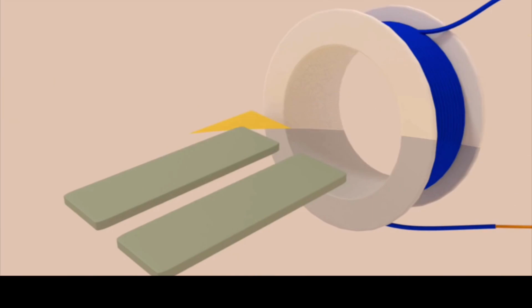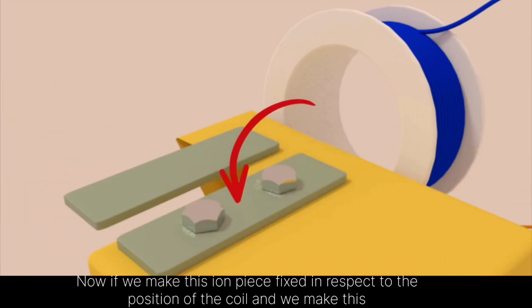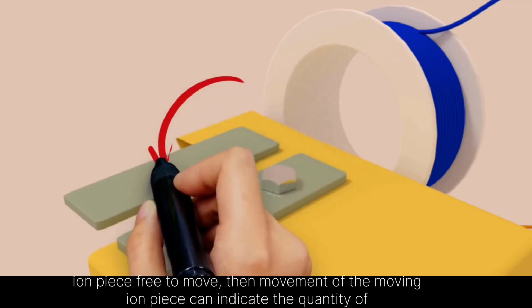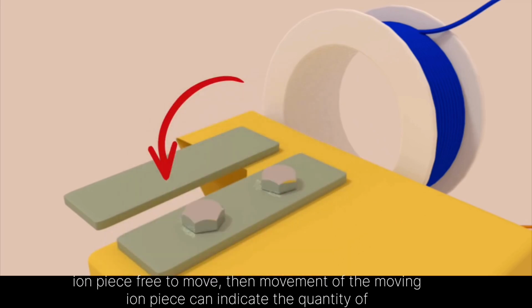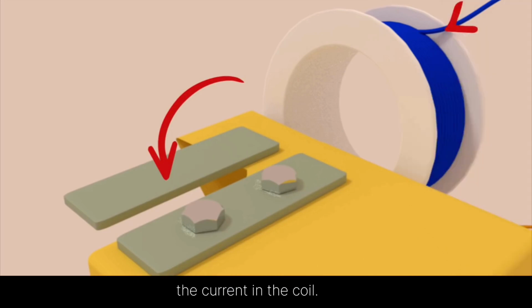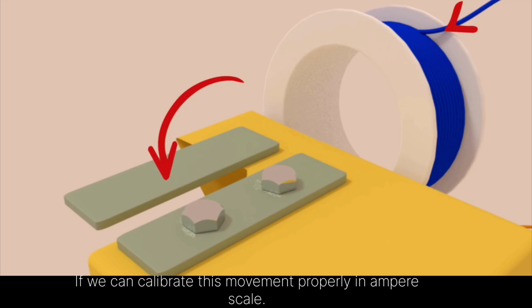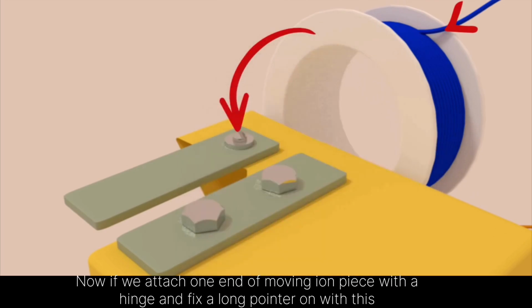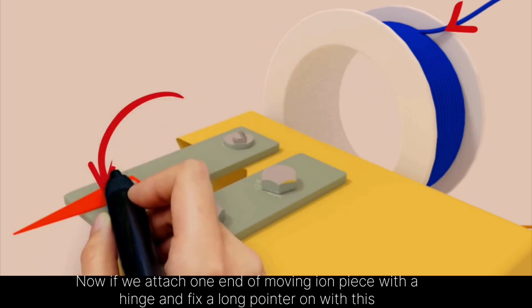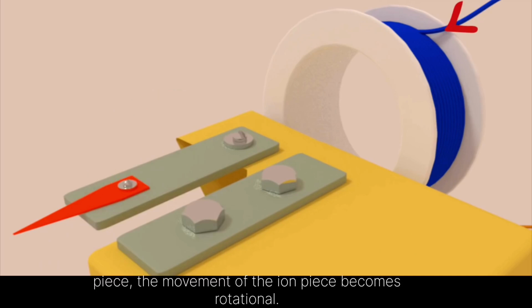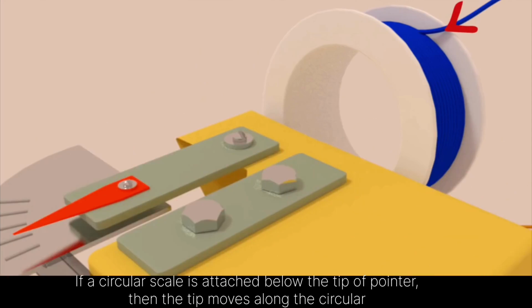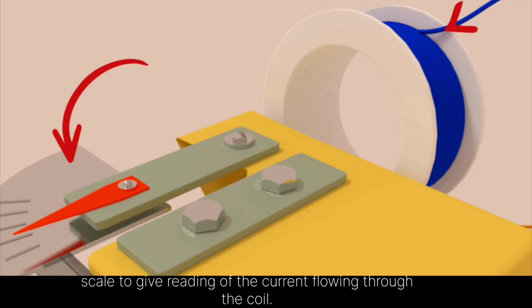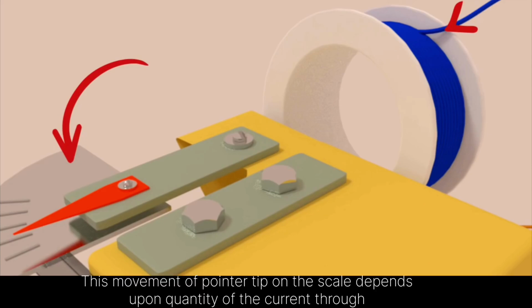Now, if we make this iron piece fixed with respect to the position of the coil, and we make this iron piece free to move, then the movement of the moving iron piece can indicate the quantity of the current in the coil, if we calibrate this movement properly in an ampere scale. If we attach one end of the moving iron piece with a hinge and fix a long pointer with this piece, the movement of the iron piece becomes rotational. If a circular scale is attached below the tip of the pointer, then the tip moves along the circular scale to give the reading of the current flowing through the coil.